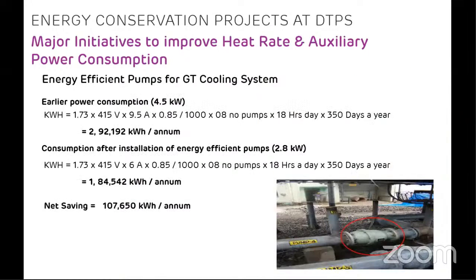Right. Moving on, in our plant we have a generator transformer, which is the major transformer that converts the power from the generator to a higher voltage level. Now these transformers have cooling fans and pumps. The consumption of the cooling pumps installed by the original equipment manufacturer was 4.5 kilowatt, as you can see here. Now we have installed new energy efficient pumps which were available in the market. They consume only 2.8 kilowatts of power.